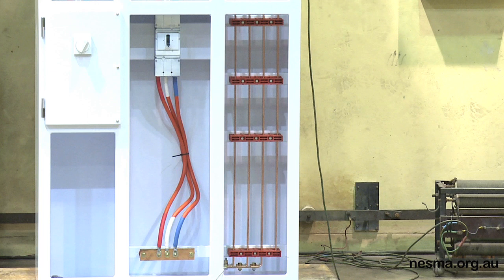Now, Mark was incorrect. I think he said it was a 1 second test, but that test was only 0.2 seconds. So, as you look at the screen, the far left-hand busbar was the phase that had the asymmetrical peak put onto the busbar system, and the two adjacent phases, or the two middle bars, were in the return path. So it was a three-phase test. The current level was 50 kA RMS, and the asymmetrical peak was 105 kA peak.